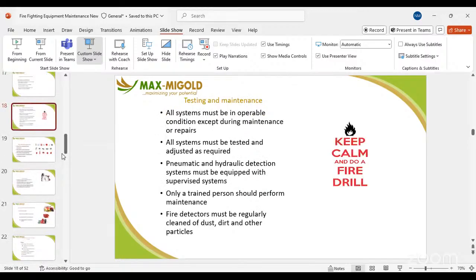Next slide, please. Yeah. So all systems must be in operable state, except during maintenance or repairs. Meaning that there must be no downtime, no defect. And if there is any defect, this should be corrected immediately. After this, all systems must be tested and adjusted as required. So you balance the fire pump, you balance the radius of coverage of the smoke detectors and what have you. If there is a hydraulic detection system or pneumatic, so either using fluid or using air, this must be supervised, that is, manned.